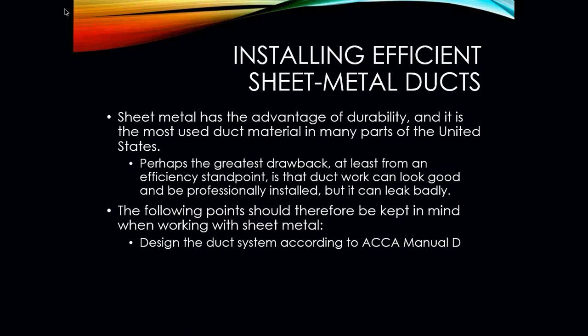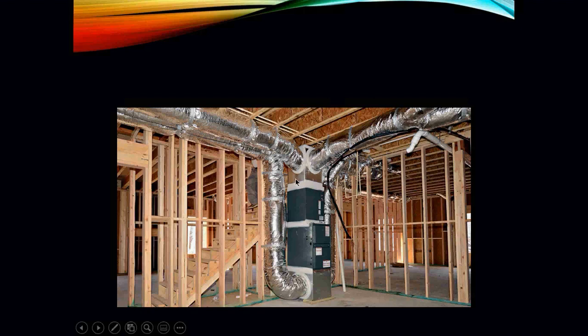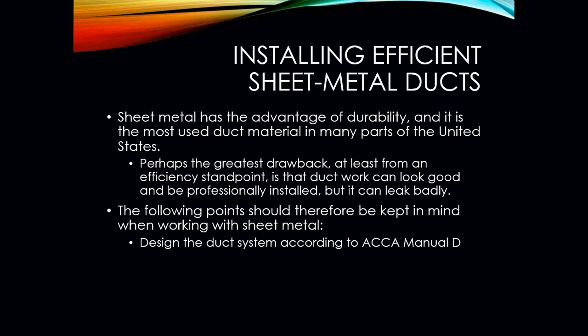installation of ductwork that may be possibly leaking, you are going to seal all of your joints like you see in this picture. All of this white stuff, this stuff here, that is all duct sealant. All of the joints that the ductwork has is going to be sealed with that duct sealant. That is what's going to be used to prevent leaks or extreme leakage. The following points should therefore be kept in mind when working with sheet metal.